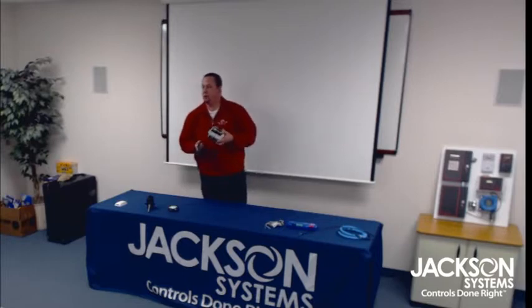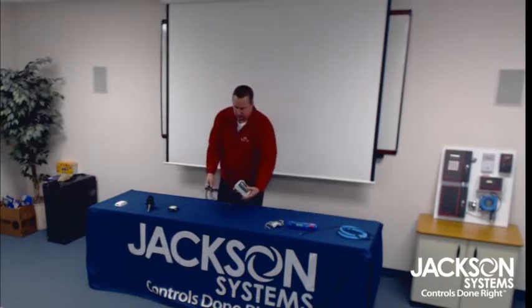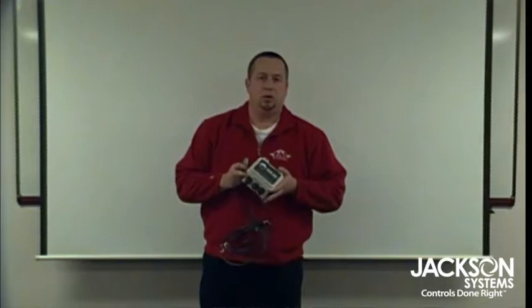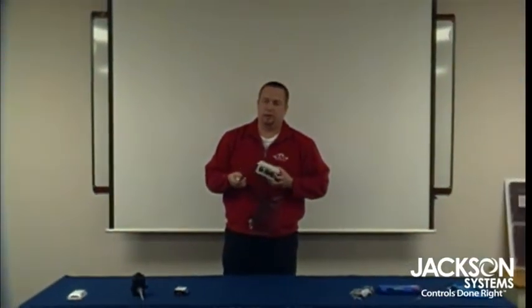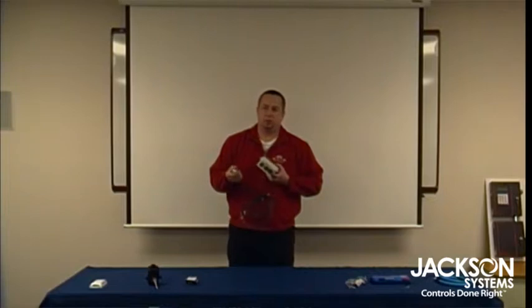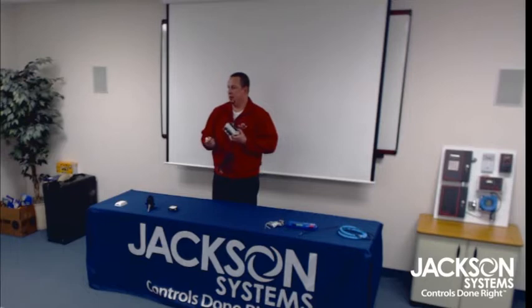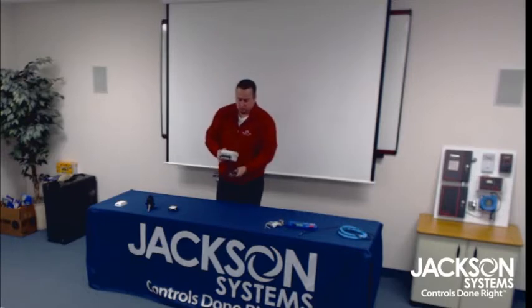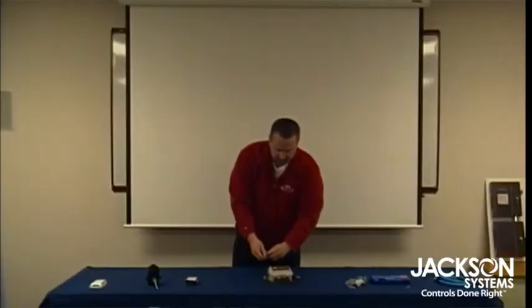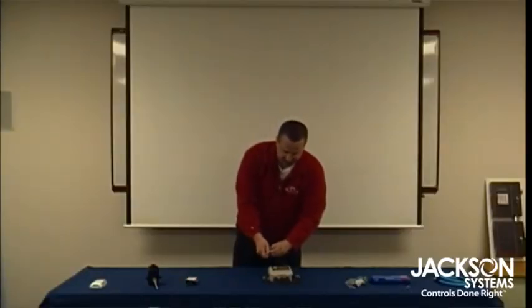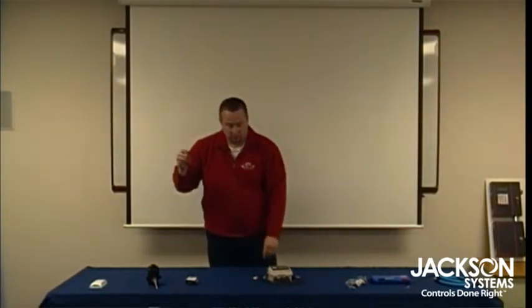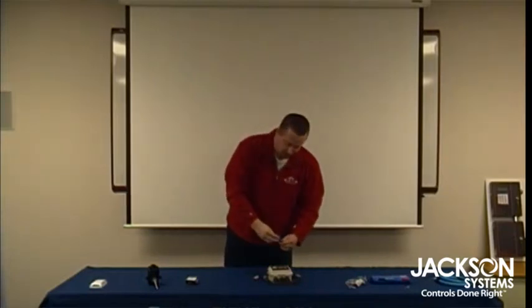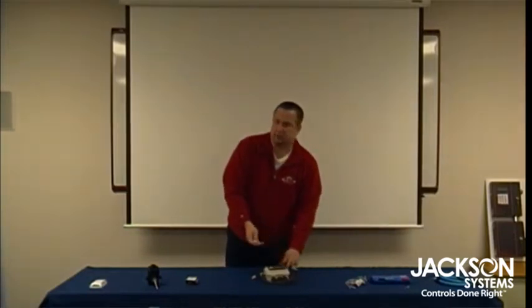This is more of a wet differential pressure, so on pumps. Our competitors have the sensors installed right inside this enclosure, and what you have to do there is run plumbing to it. A lot of times to turn it on, you have a 3-valve or a 5-valve manifold, which costs a lot more money to install. Our sensors are right on the cable to the Packard fitting, so you can actually take the sensor right off and plug it into the high and low side of the pump. So instead of hiring a plumber, you can actually install it yourself.